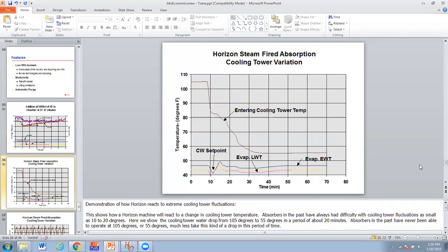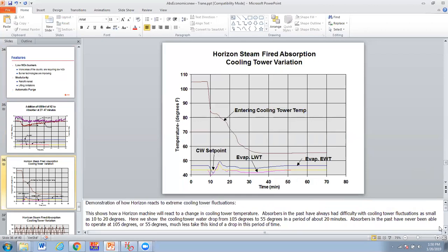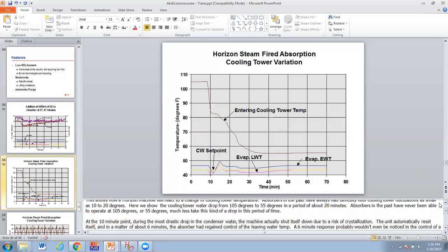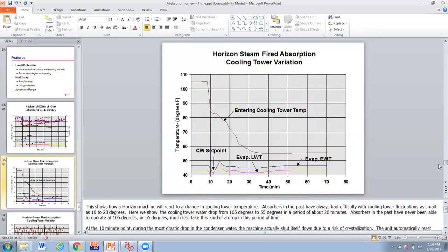Now let's see what happens if we start jerking the condenser water temperature around. Let's take a look at this one. This one shows how the Horizon machine will react to a change in cooling tower temperature. In the past, absorbers have had difficulty with cooling tower fluctuations as small as 10 or 20 degrees.